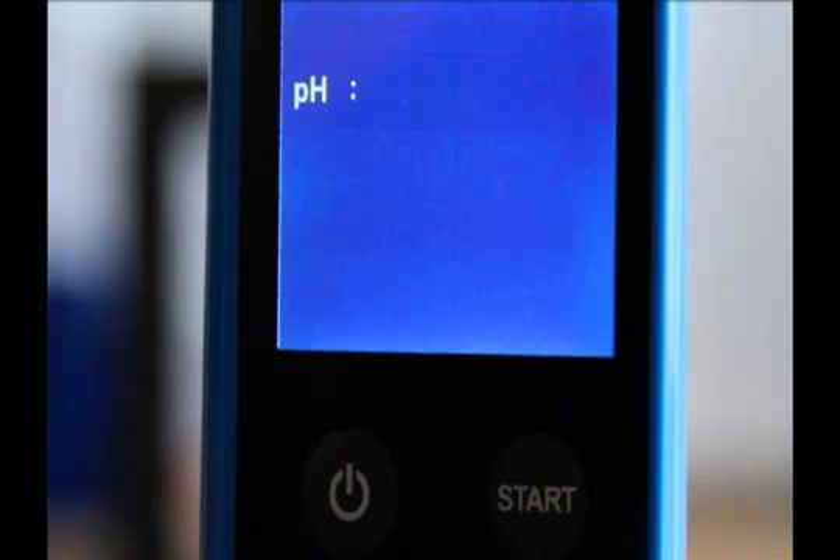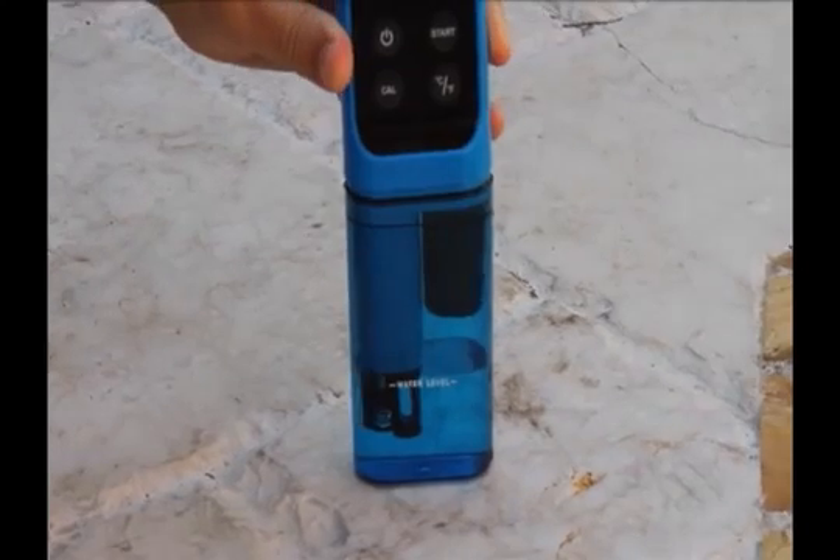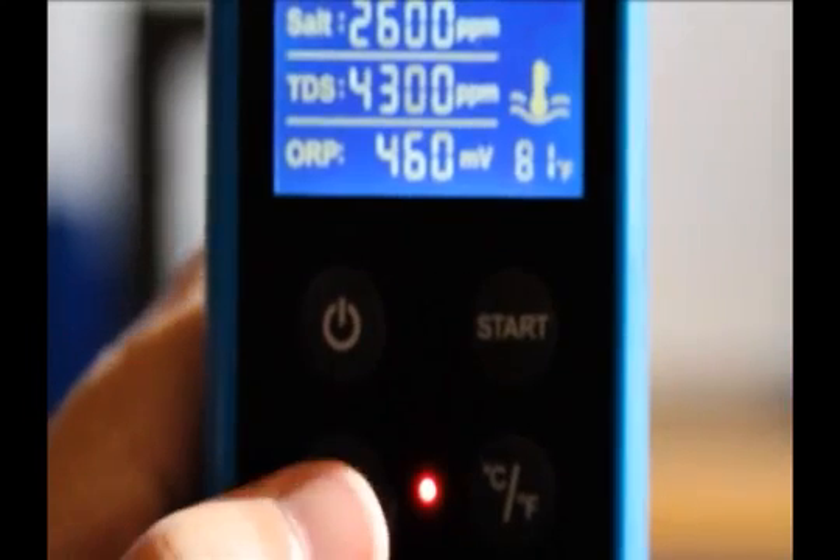Press the on/off button to turn the Safe Dip on. Press the CAL button for more than three seconds to get access to the pH calibration mode. Place the electrodes in the buffer solution and wait a few minutes for the temperature of the probes to reach the temperature of the sample.